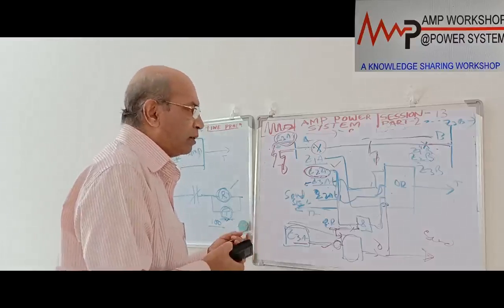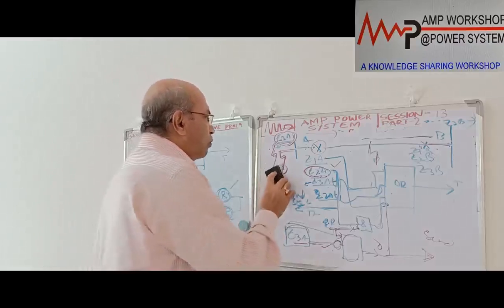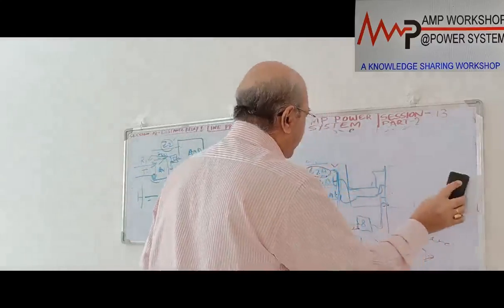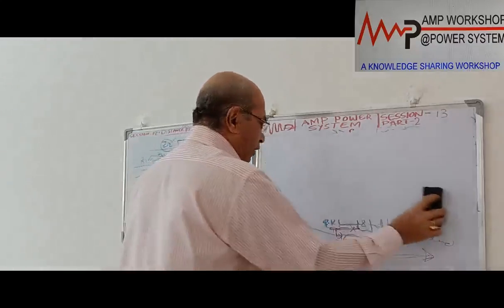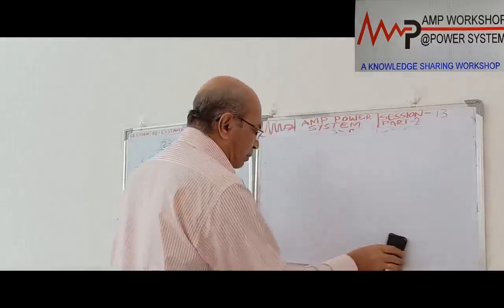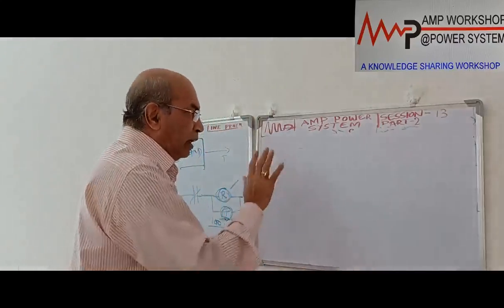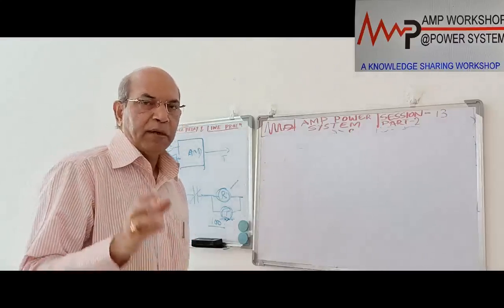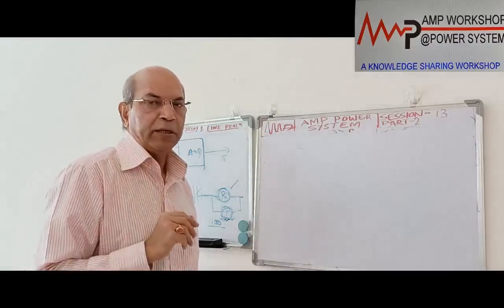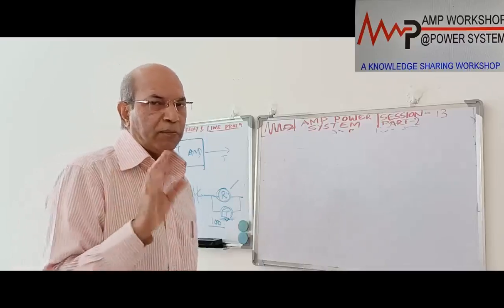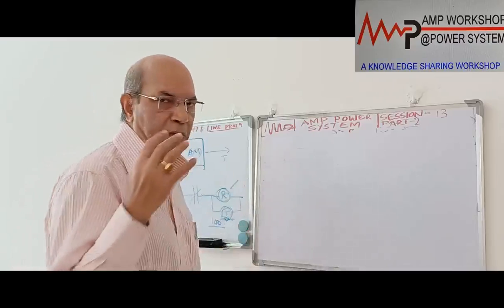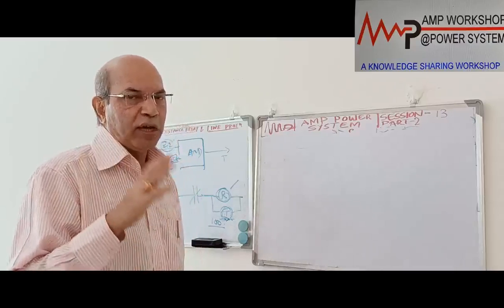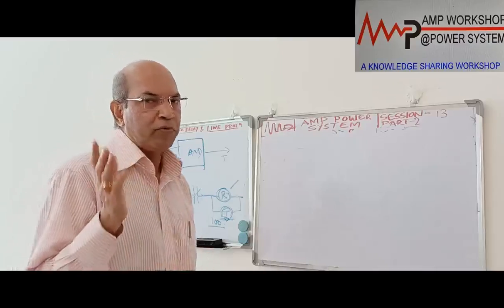We have discussed all these schemes. Now we will go to the application of the various schemes or protection relays in the case of various types of transmission line. We can say that the permissive scheme is a very secured scheme, but the blocking scheme is more dependable, and the hybrid scheme is a compromise of the two. Which scheme will be accepted for any protection, case to case we have to analyze and evaluate.